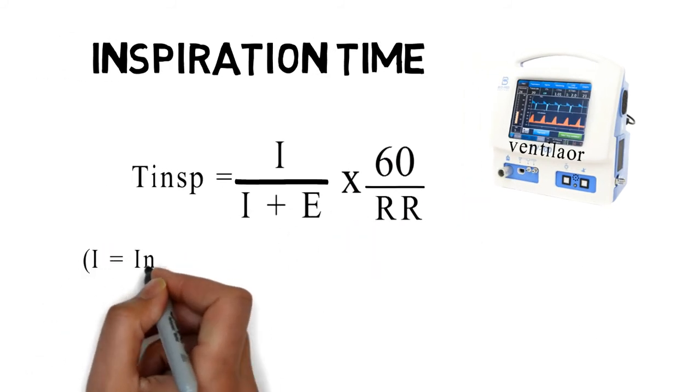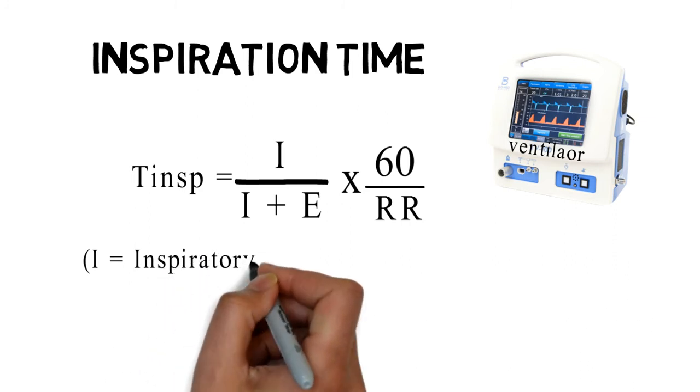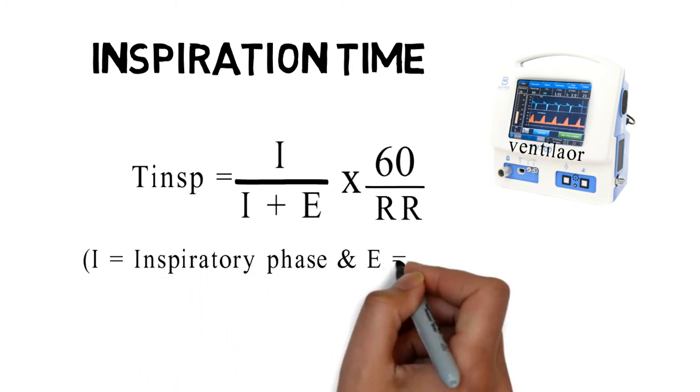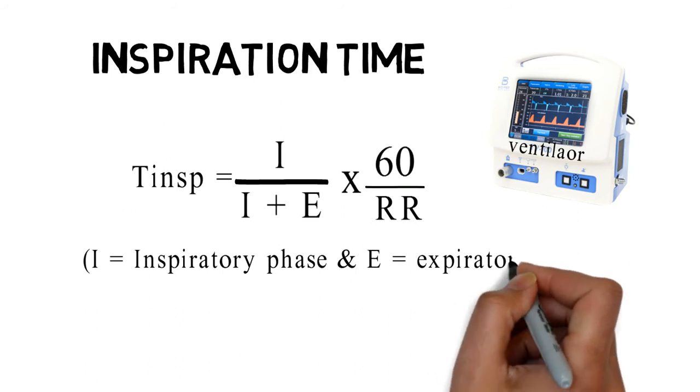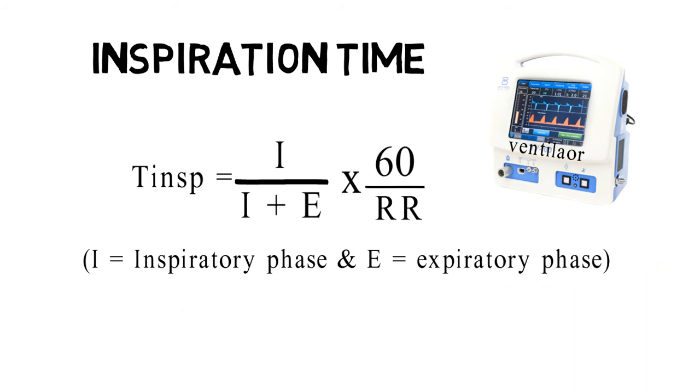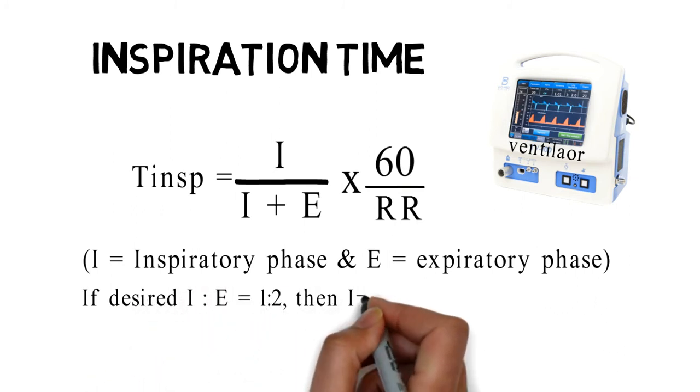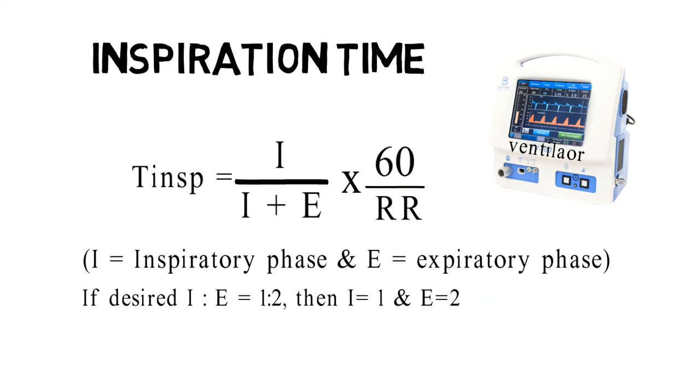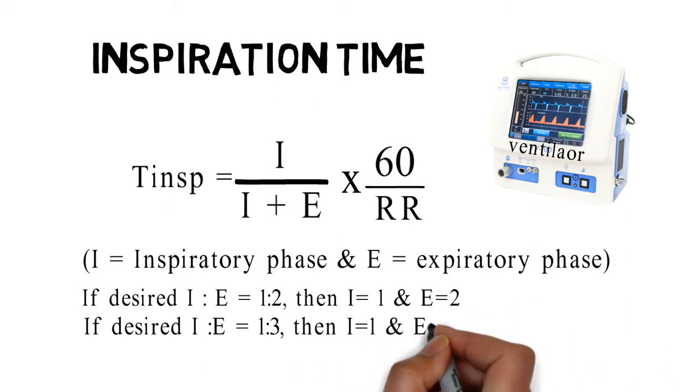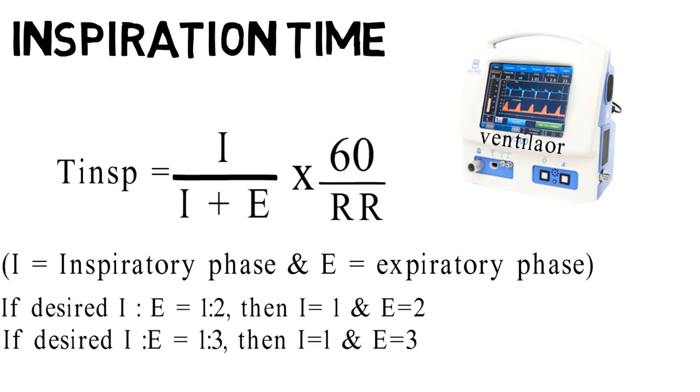Where I is the inspiratory phase and E is the expiratory phase. If the desired IE ratio is 1 to 2, then we will put I equals 1 and E equals 2 in the formula. Similarly, if desired IE ratio is 1 to 3, then we will put I equals 1 and E equals 3 in the formula.